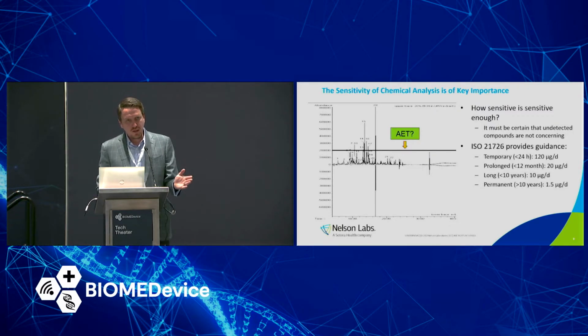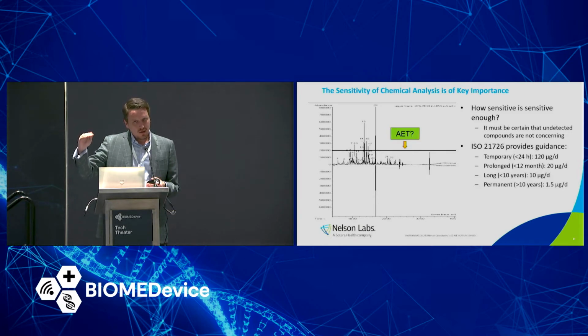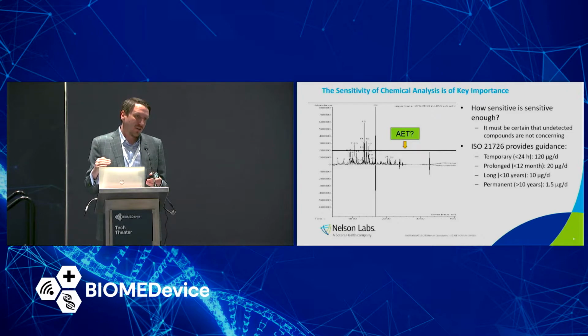We were doing that for a few years until about 3 years ago, when the FDA was like, what about the fact that when you screen, it's more like an estimated concentration? And so actually, there's a little bit of wiggle room when you estimate how much of that chemical is there, and you could be off. So maybe it's reported at 1 microgram per device, but since we know that in screening methods this estimation can be a little bit off, it might actually be at 3 micrograms per device. And then it would be above the TTC. So now we take the TTC, this threshold of toxicological concern, and divide it by an uncertainty factor that accounts for the fact that when we screen and we don't have an authentic standard for everything that might randomly come from a device, whatever we see, even considering this uncertainty, wouldn't be above the TTC.